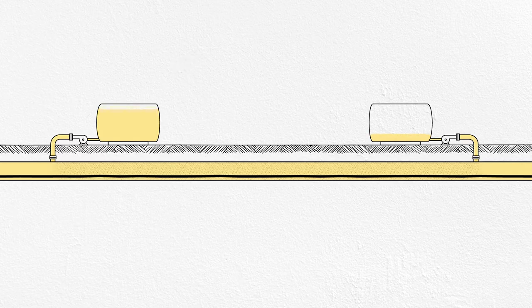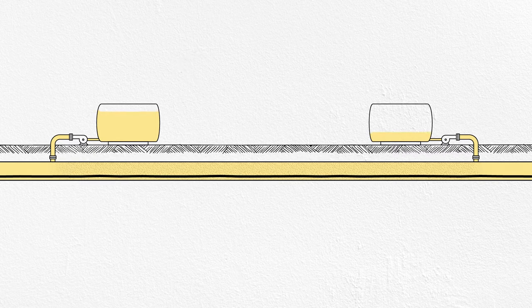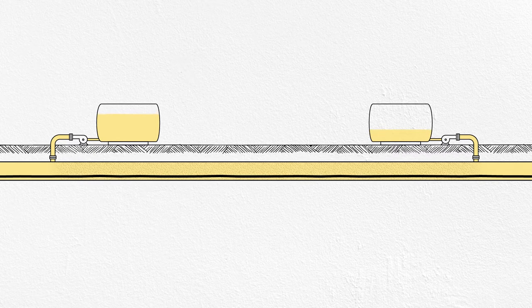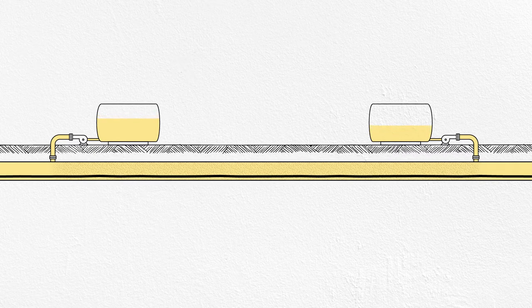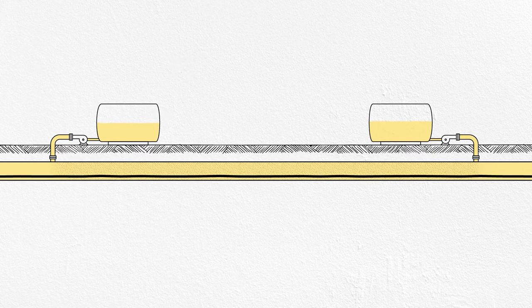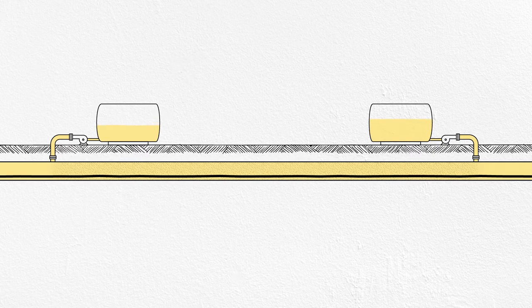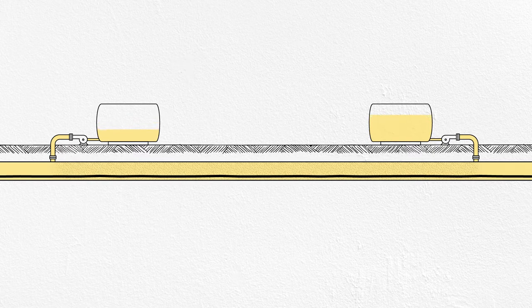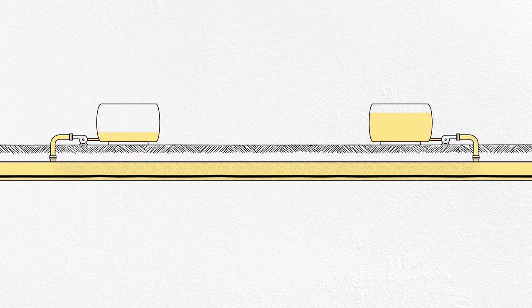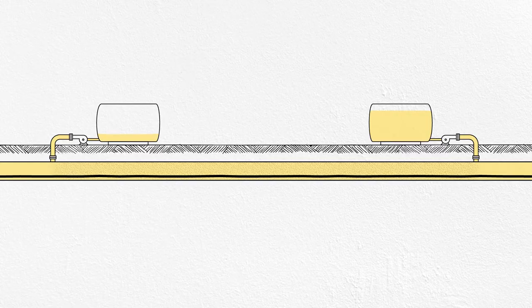The rating of a transmission line—in other words, how much power it can deliver—is almost entirely based on temperature. All conductors, with rare exceptions, have some resistance to the flow of electric current, and that creates heat, which will eventually damage the conductors and insulation if it builds up. The more heat you can remove, the more power you can push through the line. That's a major benefit of pipe-type oil-filled cables. They're surrounded by a gigantic liquid heatsink that can be circulated to keep the temperature down and prevent hot spots from forming in the lines.